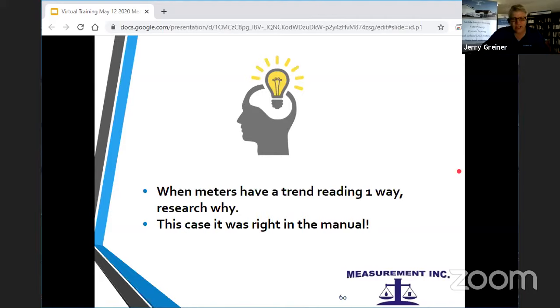In this case, it was right in the manual. It tells you exactly the amount that it's out, and we could calculate it, and it was exactly what we were seeing in the field. So sometimes if all your meters are trending a certain way, and we noticed the 2-inch ones read all low and the 1-inch ones read right, what are we doing different? How come we're not proving these? We use the same proving system and the same equipment, and all of them go one way. You sometimes need to research why you're doing it all in the same direction.